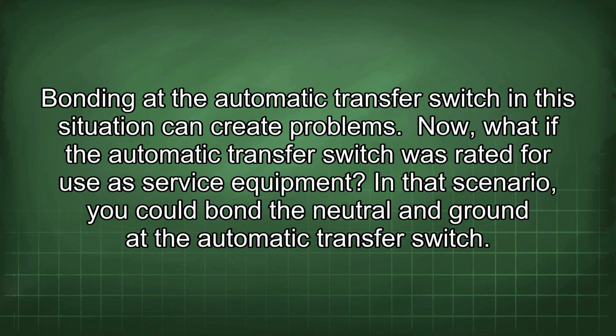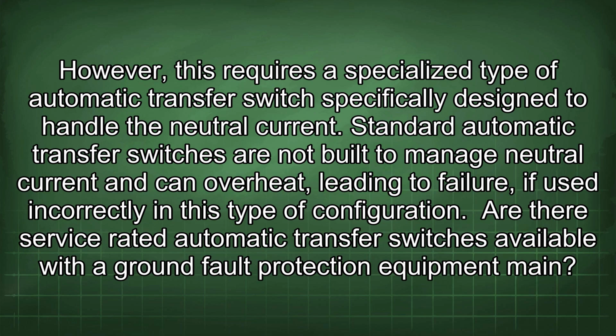Now, what if the automatic transfer switch was rated for use as service equipment? In that scenario, you could bond the neutral and ground at the automatic transfer switch. However, this requires a specialized type of automatic transfer switch specifically designed to handle the neutral current. Standard automatic transfer switches are not built to manage neutral current and can overheat, leading to failure if used incorrectly in this type of configuration.